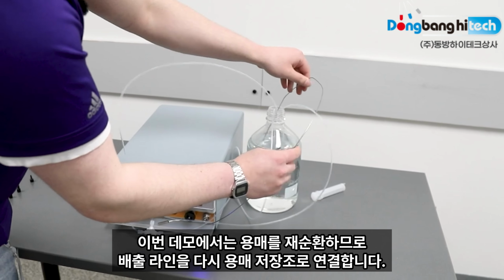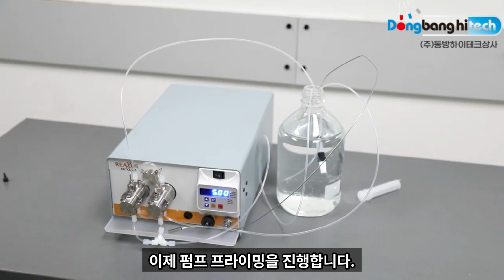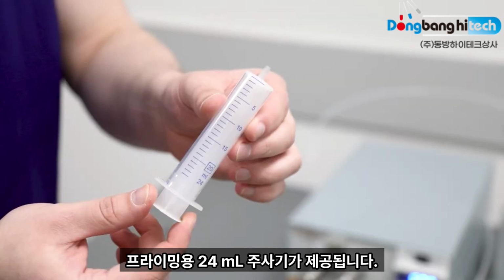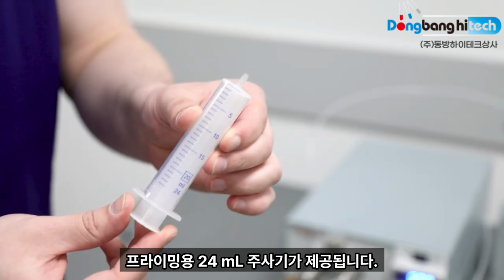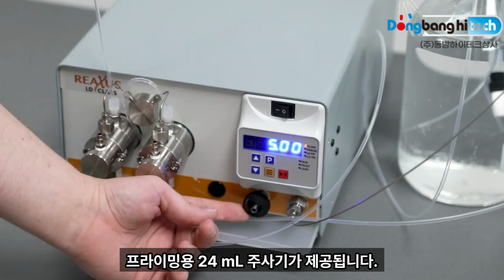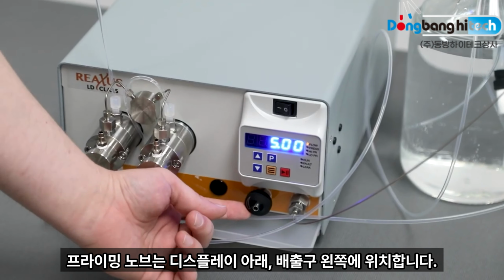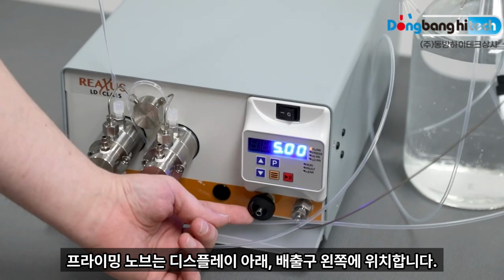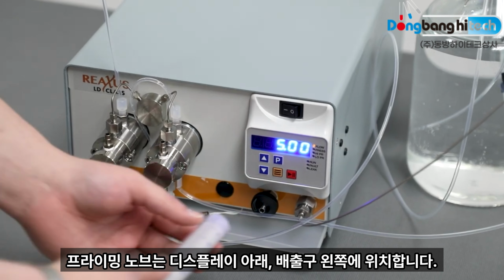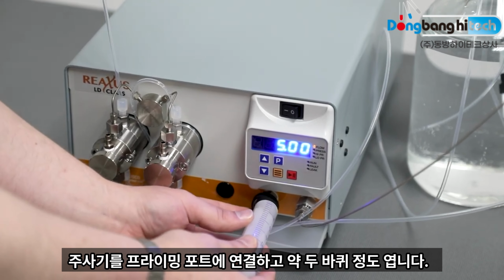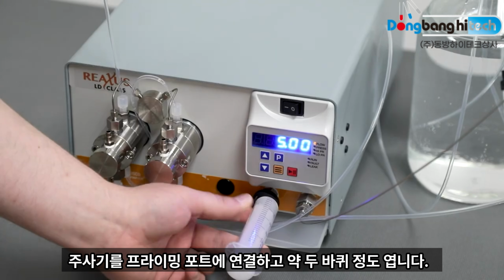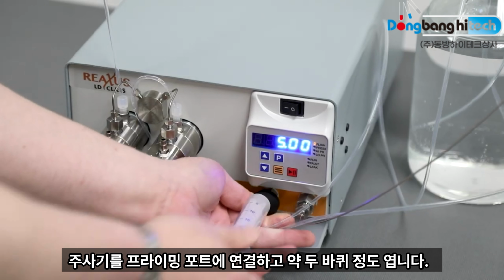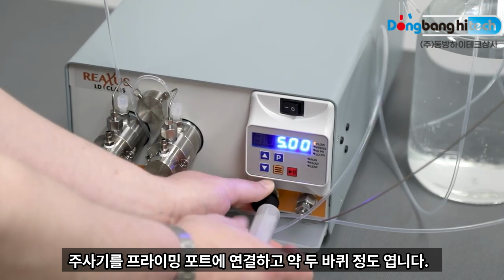our solvent reservoir. Now what we're gonna need to do is prime our pump. There will be a supplied 24 milliliter syringe intended for priming the pump, and we will have our prime knob located to the left of our outlet underneath our display. To prime, I'm going to insert my syringe into the luer lock on the prime knob and open roughly 2 turns.